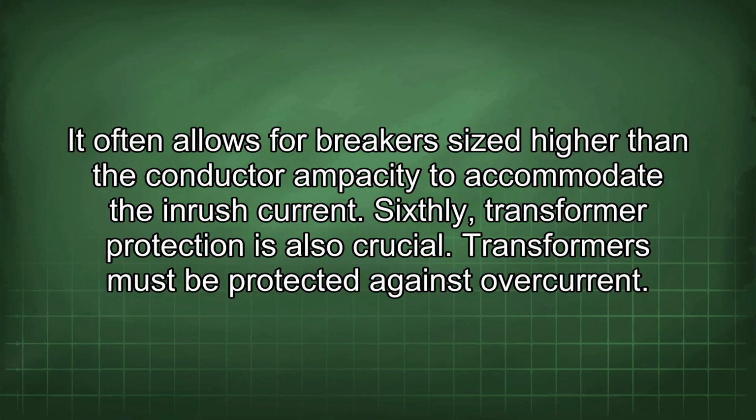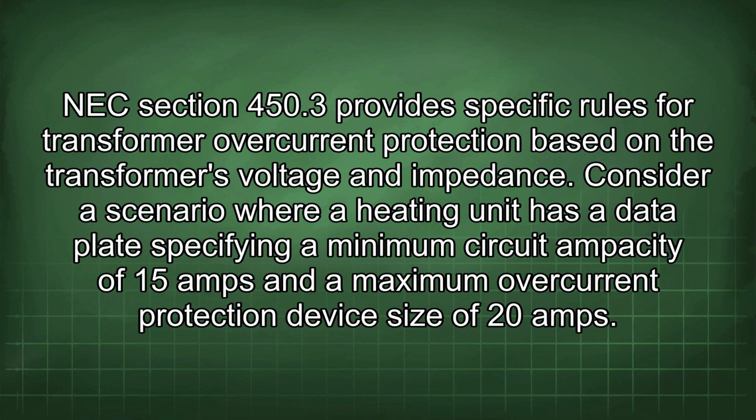Sixthly, transformer protection is also crucial. Transformers must be protected against overcurrent. NEC Section 450.3 provides specific rules for transformer overcurrent protection based on the transformer's voltage and impedance.